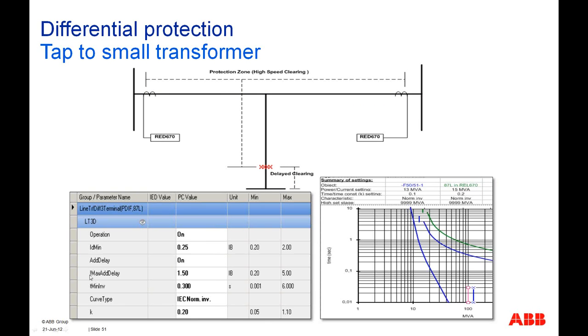So these are the settings which you can make in RED 670 to detect the faults on the small transformer. We have to put in a value of ID min high, as well as a delay. In this case, the inverse time characteristic has been chosen, and the time dial is 0.3 and the K factor is 0.2. This type of protection can also be used in some specific cases where we have a small tapped power transformer in the transmission line.